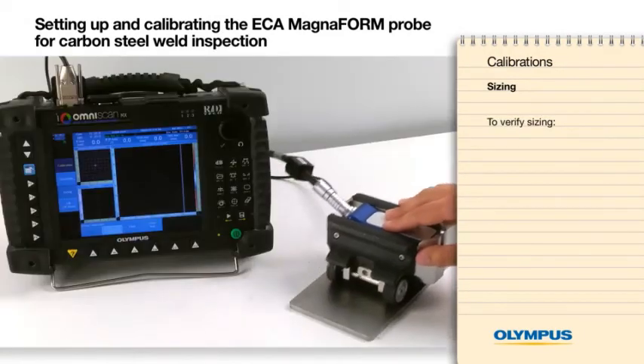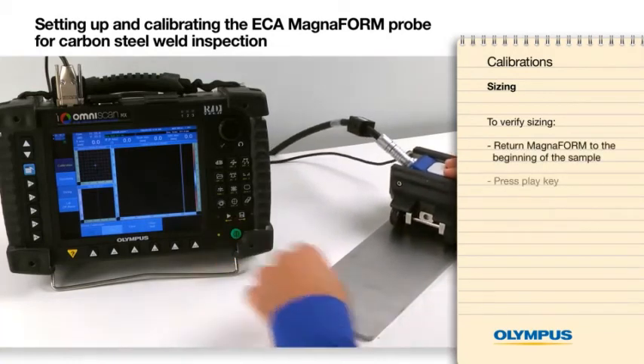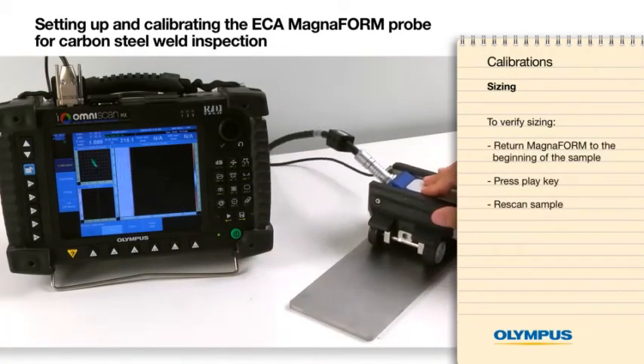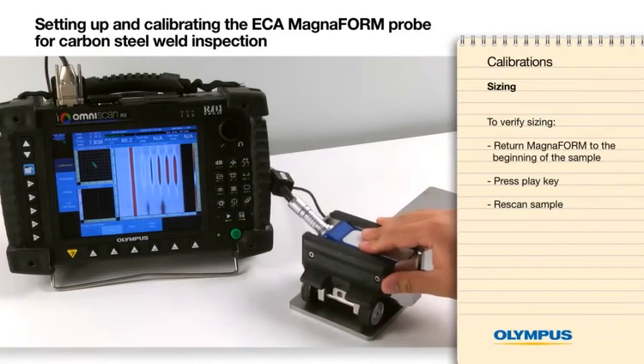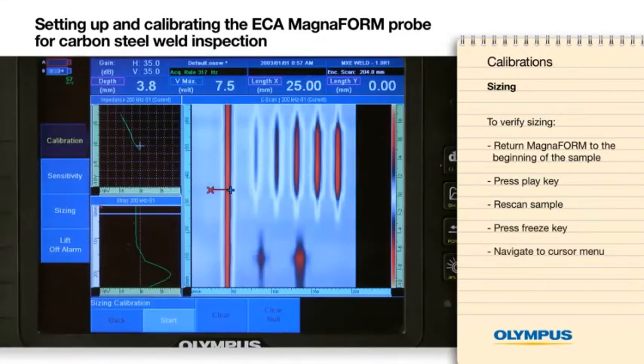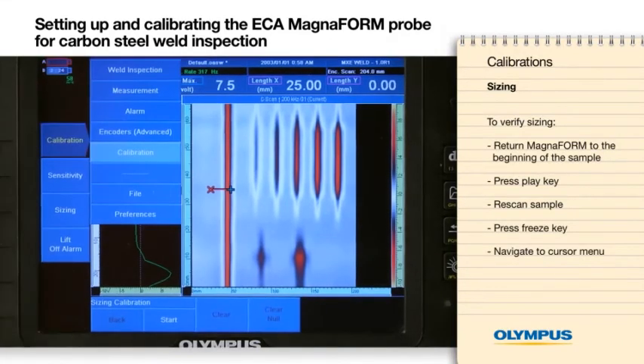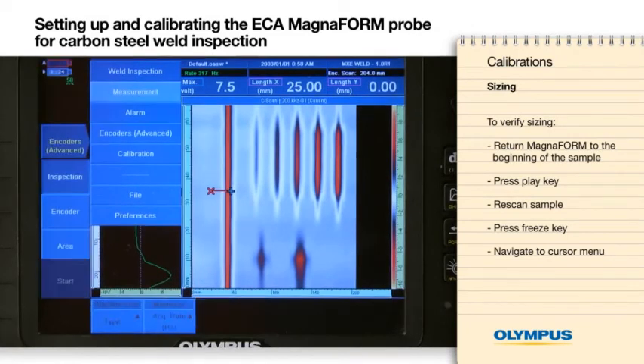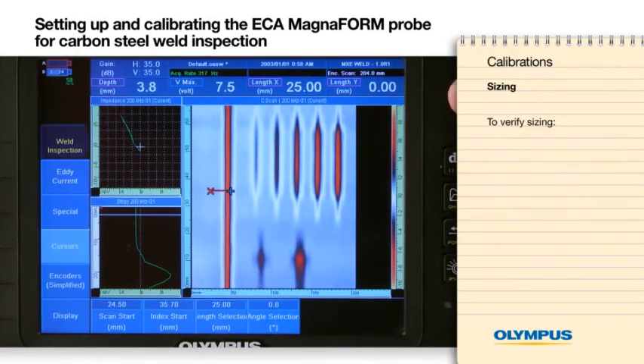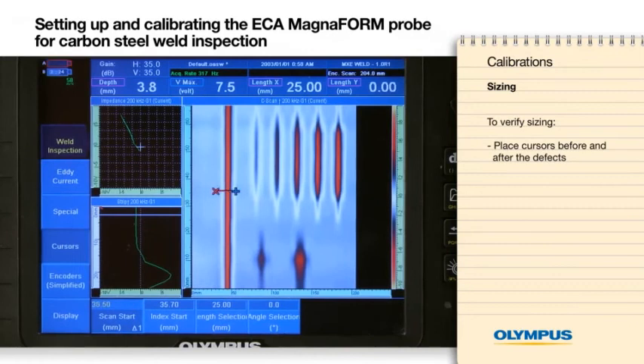To verify the sizing, place the MagnaFORM at the beginning of the sample. Press the play key and rescan the sample. Press the freeze key and then navigate back to the cursor menu. Place the cursors before and after the defects and validate the depth reading.